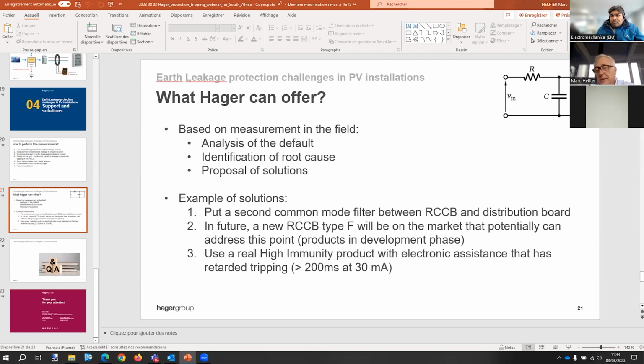I can take the question. I will discuss with our battery inverter experts we have in the group. I will ask them if there are some rules about the cable cross section for earthing of the inverter and battery. I will send the answer to ElectroMechanica, and they will forward you the answer then. I see Hercules did respond here. His recommendation is a minimum of 6 millimeter for the earth cable. And normally there is no current in the earth cable, so I'm a little bit surprised, but I will double check.